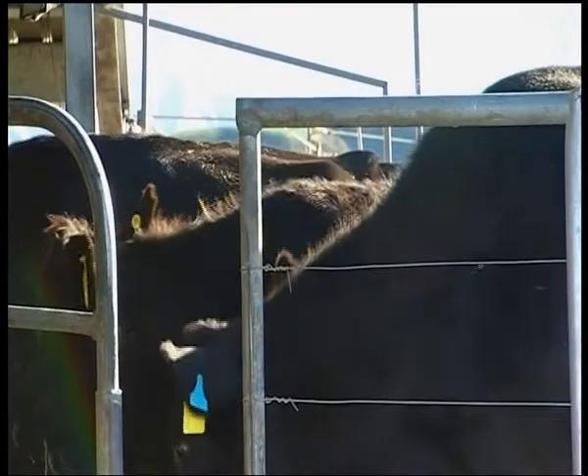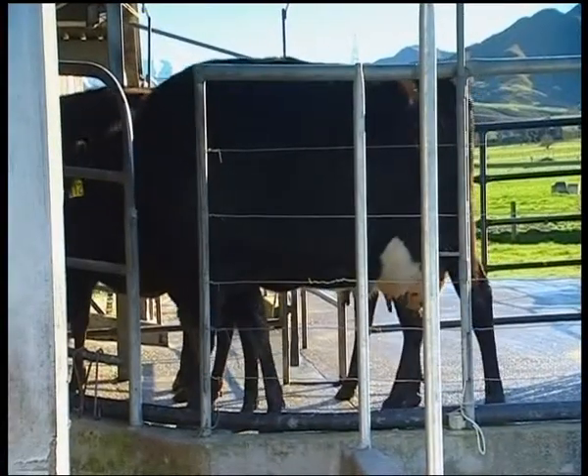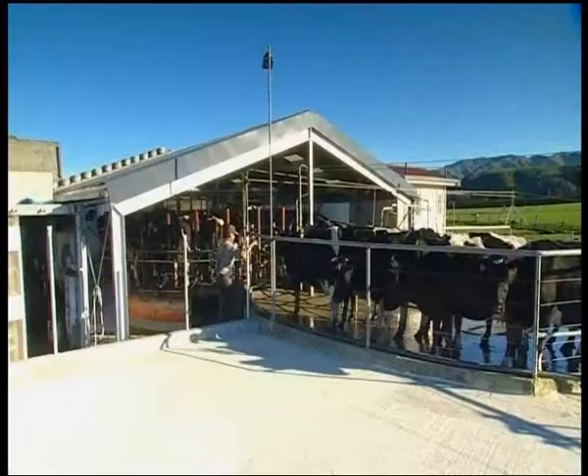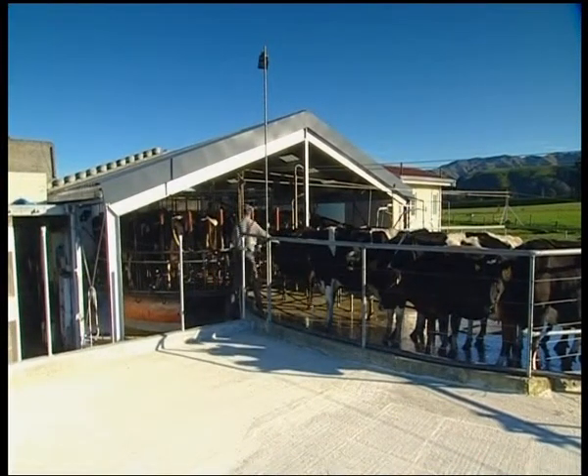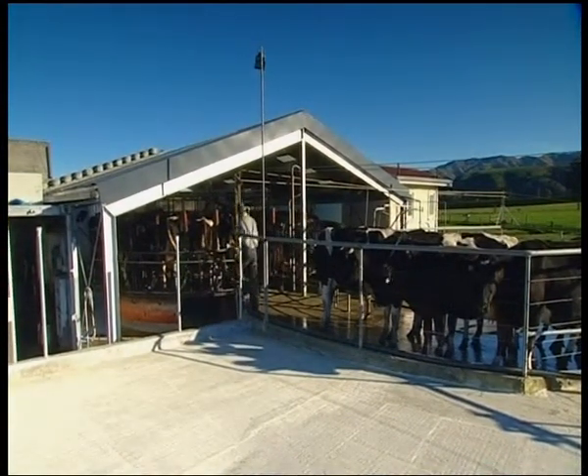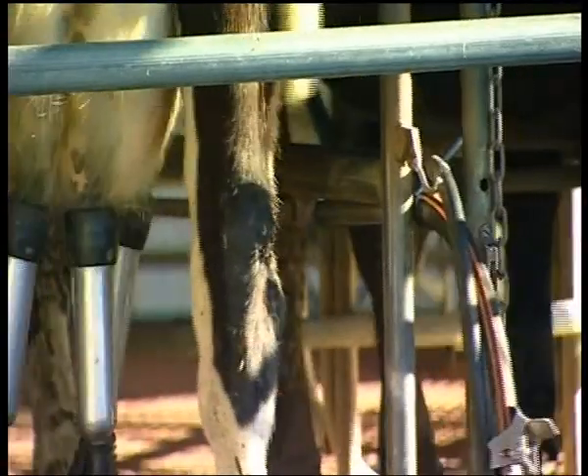With the two different types of stray voltage, with the neutral related one, the cow won't want to step across a particular point or won't want to touch 2 points because it's a potential difference point. So it's like putting your tongue on a 9-volt battery, she'll feel it across the point. With the harmonic one, it's more like when you slide out of a car and reach back and get a whack off the door handle. It's more of an electrostatic discharge. And remembering a cow's 15 times more sensitive than a human.